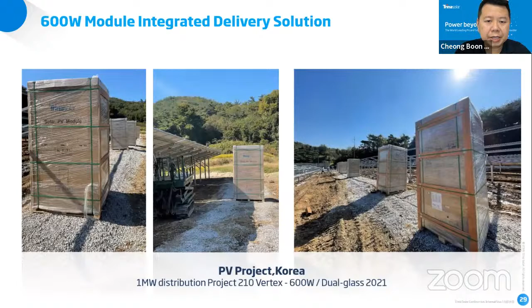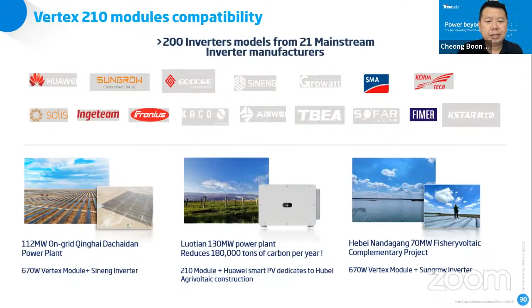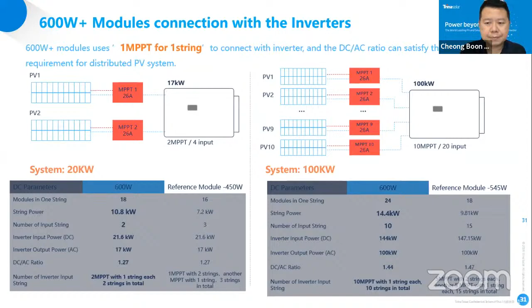As mentioned earlier, Trina Vertex modules for the 19, 20, 21 series use a low voltage, high current design. We've worked with various mainstream inverter suppliers to ensure compatible models. For example, depending on the model you choose, we are able to use one MPPT for one string to connect with the inverter. Although the total number of modules might be less compared to a conventional two-string per MPPT, because of the higher power bin of each module, we are still able to meet the DC-AC ratio requirement of the projects.